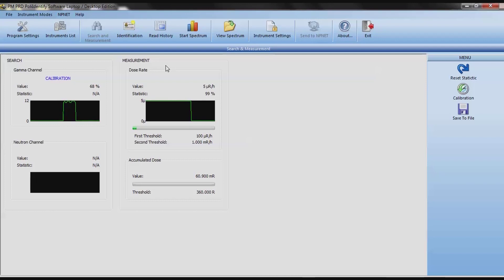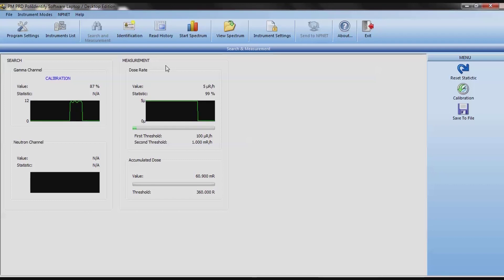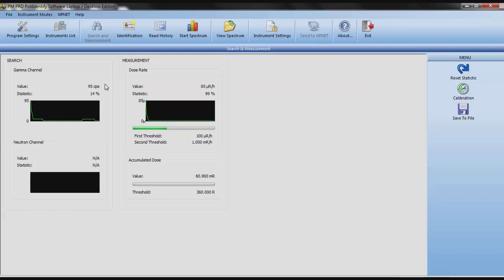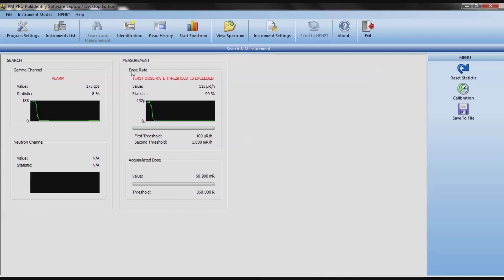Alright, we should be getting just about done now. As you can see, it doesn't monitor anything while it's calibrating. Okay, now we are done. So we can put the box beside the device again. And we should, oh there we go, we get a really immediate alarm. Look at that. Look at that, count rate and counts per second, very high. Definitely something in that box. Now, let's identify it.